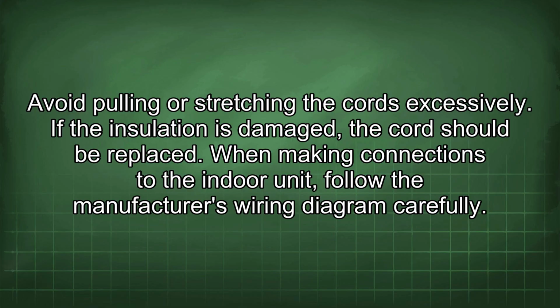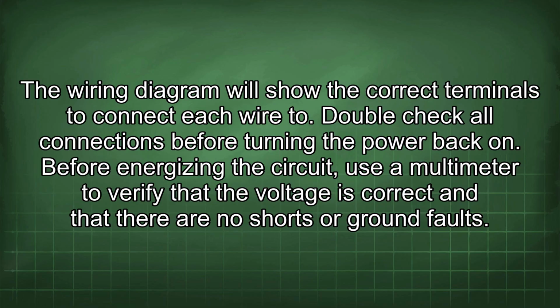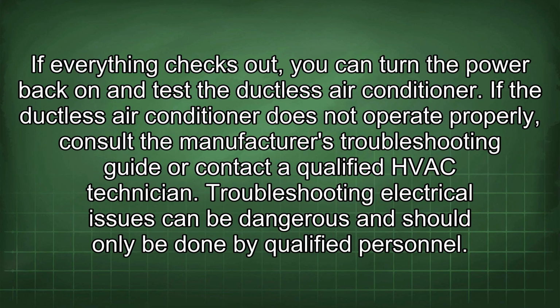When making connections to the indoor unit, follow the manufacturer's wiring diagram carefully. The wiring diagram will show the correct terminals to connect each wire to. Double-check all connections before turning the power back on. Before energizing the circuit, use a multimeter to verify that the voltage is correct and that there are no shorts or ground faults. If everything checks out, you can turn the power back on and test the ductless air conditioner.